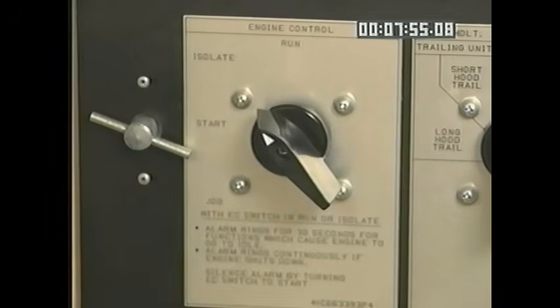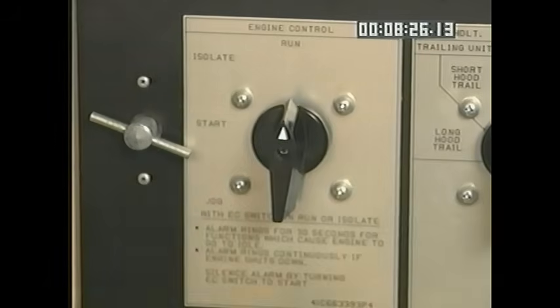The next position is isolate. When the engine is running with the EC switch in this position, the engine speed, as in the start position, is held to an idle, and power cannot be applied to the unit. In the isolate position, unlike the start position, an alarm bell sounds if the engine shuts down. When the engine is at idle and about to be operated, the EC switch should be moved to the run position. Run is the normal operating position for the engine control switch. An alarm bell sounds if the diesel engine is shut down with the EC switch in the run position.